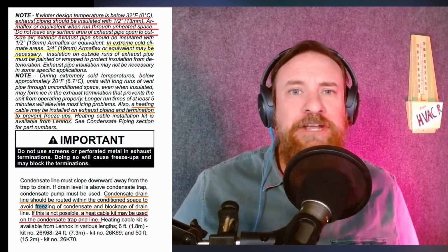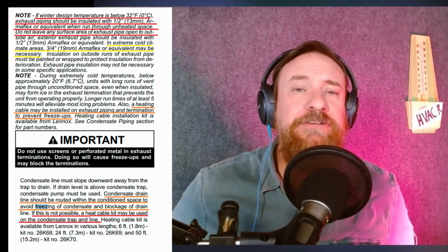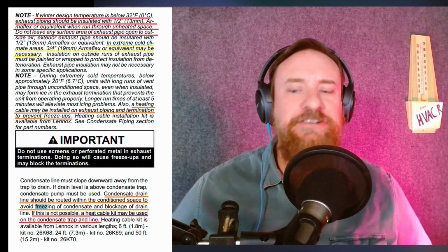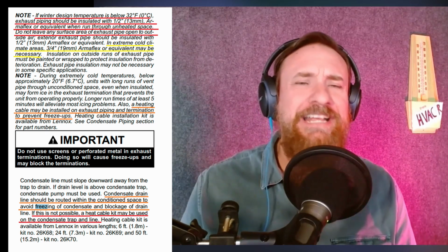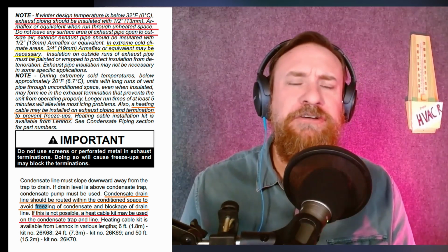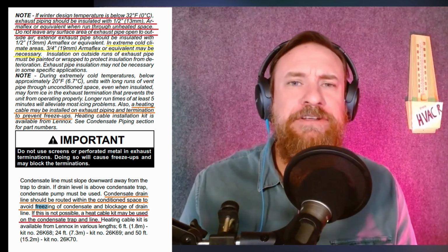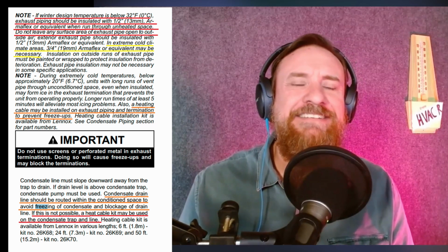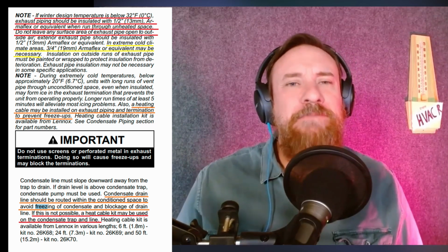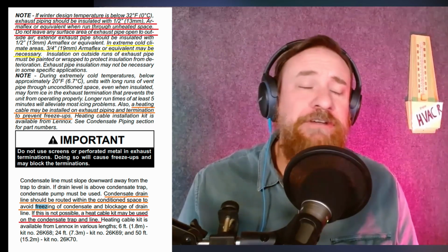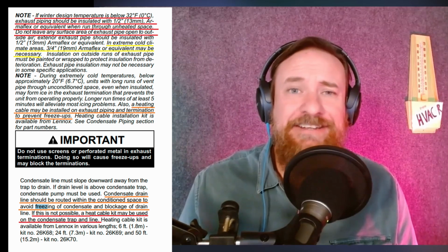Now, there are people that argue about code, but if you really look at the code, there are always exceptions, and code's difficult to read. I give you that. Some people just want to say you can't put the condensate drain in a drain line, and I haven't yet seen that to be true. We want to make sure that drain line is not going to freeze. So if we run that drain line outside, yeah, it's going to freeze up. It's going to be an issue. So we want to make sure that we drain it to a proper place. Then it's not going to be an issue, and if we do that, it's going to be fine.